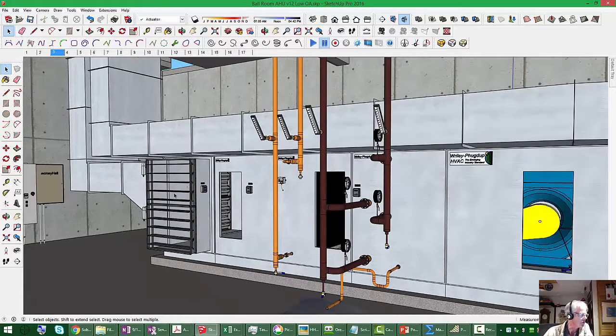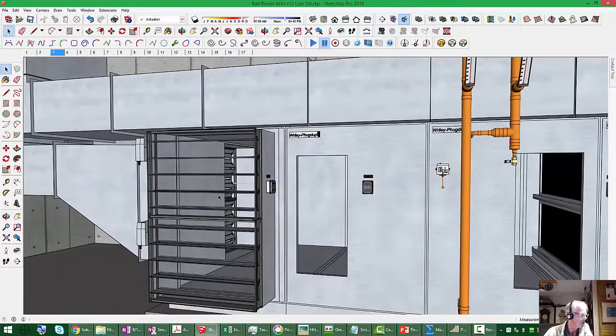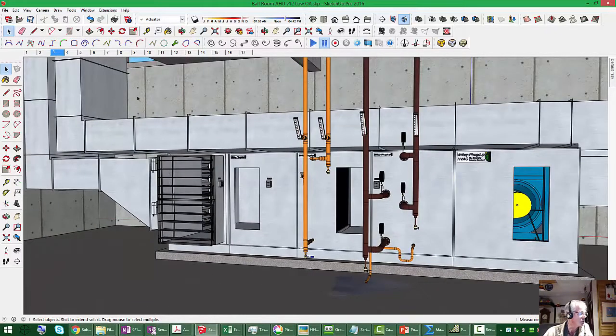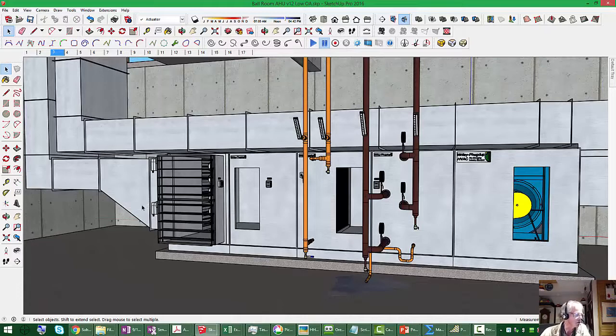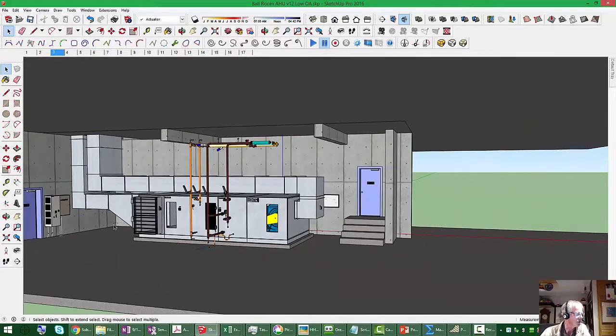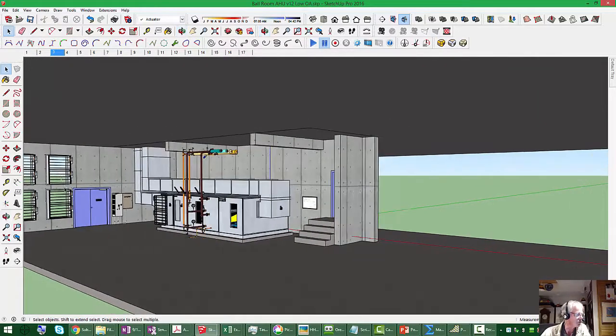These dampers here, if you look closely, basically feed air into a place where the outdoor air comes in, and there's a damper there. So this is probably the economizer section, the mixed air plenum, which would make these the return dampers, which would mean this is a return air shaft. Clearly this is a supply duct coming off the fan. So this is a return air shaft, and the mechanical room is a return air plenum, and so the dampers on the wall are the relief system. Okay. And so one thing you might ask yourself is, should those dampers be wide open or not? Right now they are.